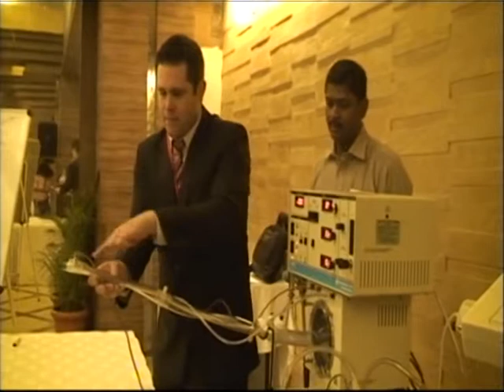There's a bias flow of gas going through that system at all times. And that bias flow in babies, you shouldn't have to set that at more than 15. For years, we were always told, set your bias flow at 20 liters a minute. However, if you set that too high, it may result in gas trapping in your baby. So what I tell people is to use the lowest possible bias flow. That's like your CPAP gas going through the system. Use the lowest available bias flow to maintain the pressure that you want to set.